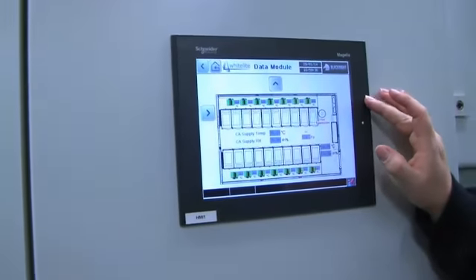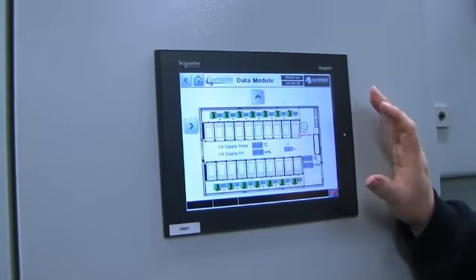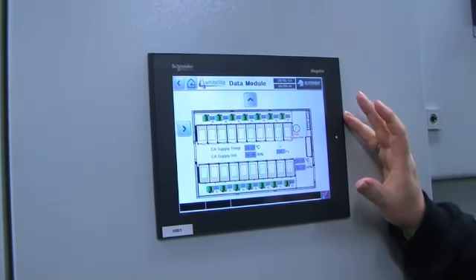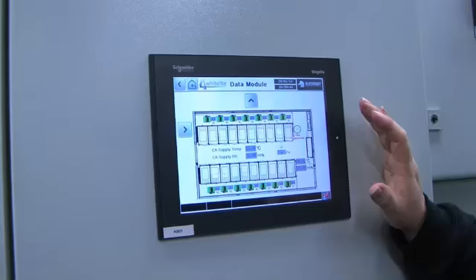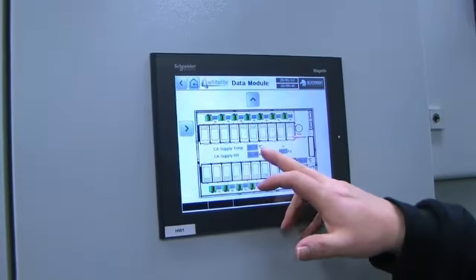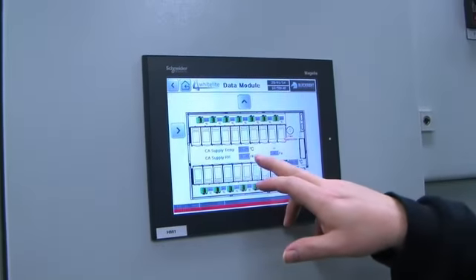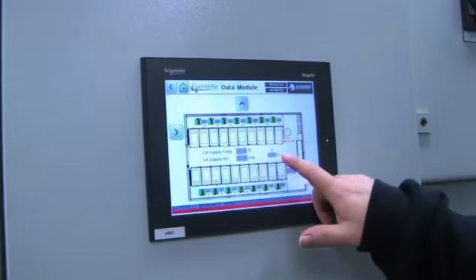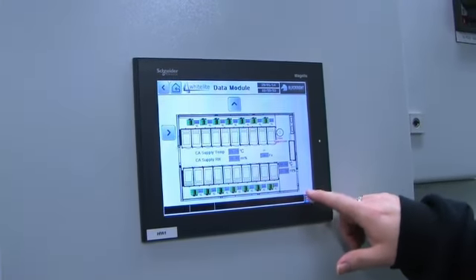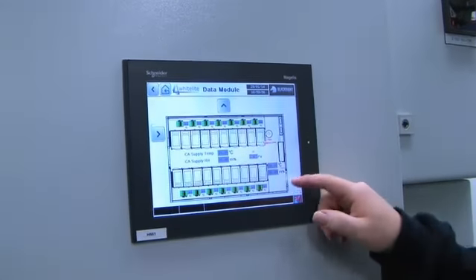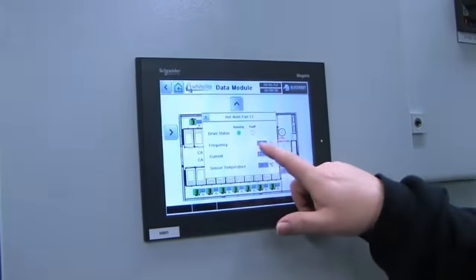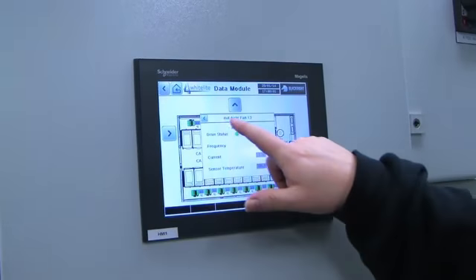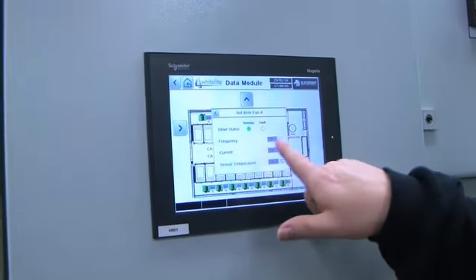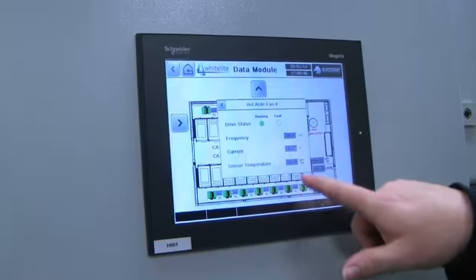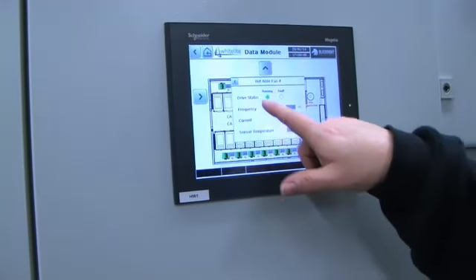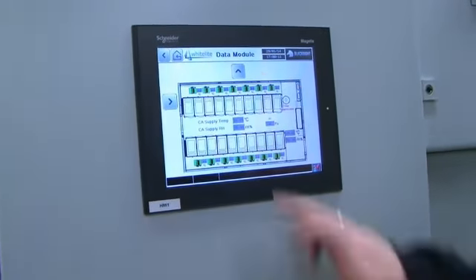Behind you, we have what we call a HMI. It's a human machine interface. So it is a piece of software and a piece of technology that allows a human, while in the data center, to see vital statistics: temperature, relative humidity, positive pressure, and whether or not a door is open. So as you see, someone just buzzed in there, the door opened and closed. You can see what frequency each fan is running at. Pick another one at random. 10.4 hertz, current is 0.7 of an amp, and it's detecting 22 degrees centigrade. You can go up top.